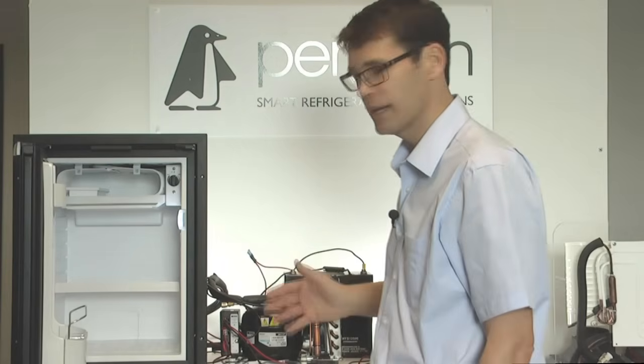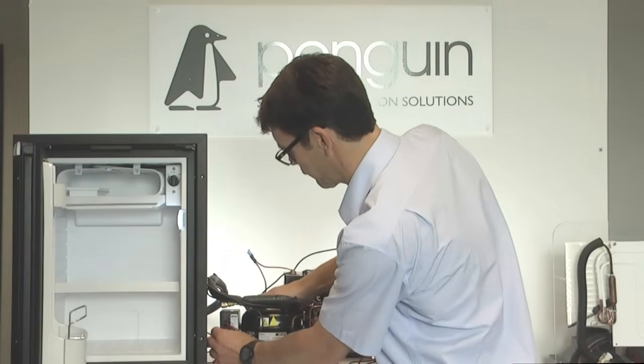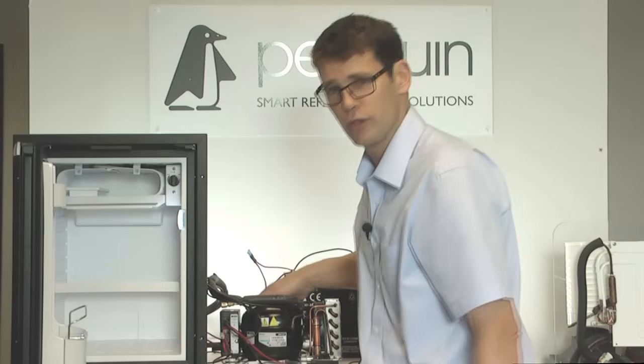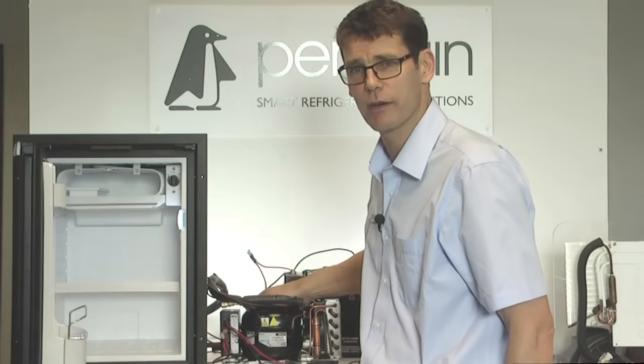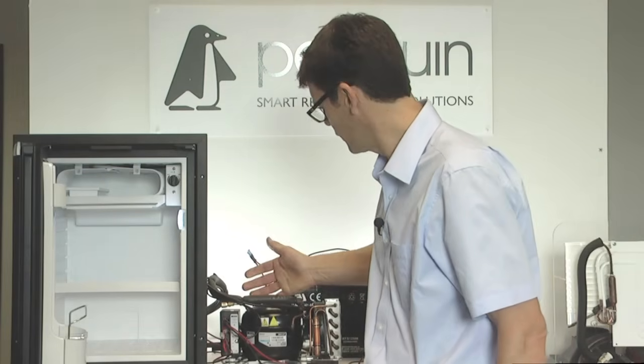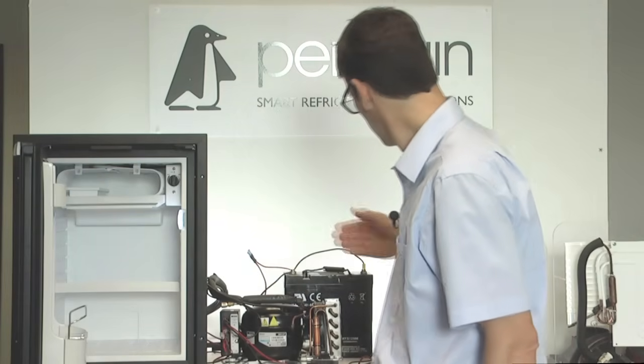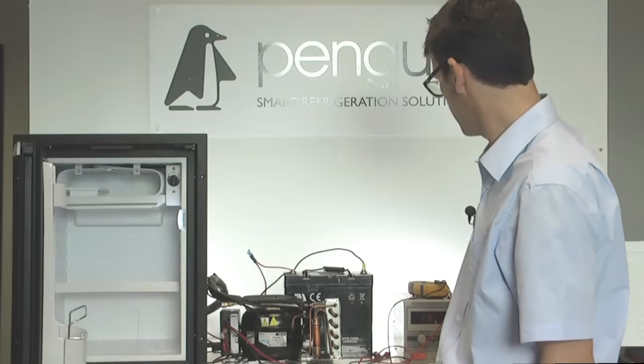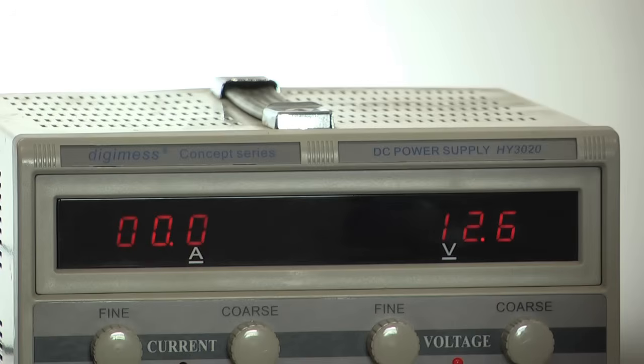It doesn't seem that the compressor is running. To confirm this, the easiest way is to unplug the fan, and you should be able to feel the compressor vibrating if it's running. I can't feel any vibration, and if I look at my amps I've got no amps running, so this compressor isn't running. So I need to work out why.